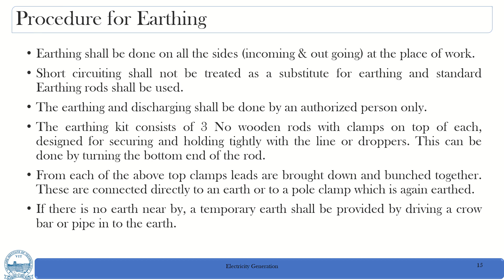The earthing kit should consist of 3 wooden rods with clamps on top of each, designed for securing and holding tightly the line or the droppers. This can be done by turning the bottom end of the rod. From each of the above, the top clamps are brought down and bunched together, and these are connected directly to an earth or to a pole clamp, which is again earthed. If there is no earth nearby, a temporary earth shall be provided by driving a crowbar or pipe into the earth.